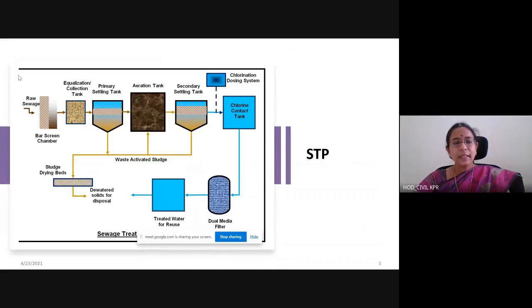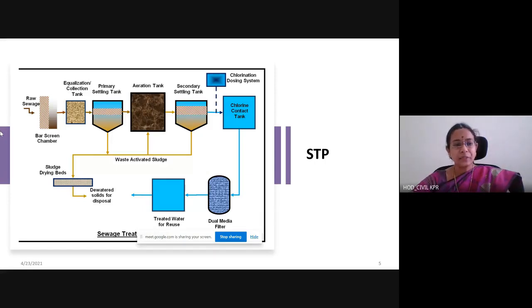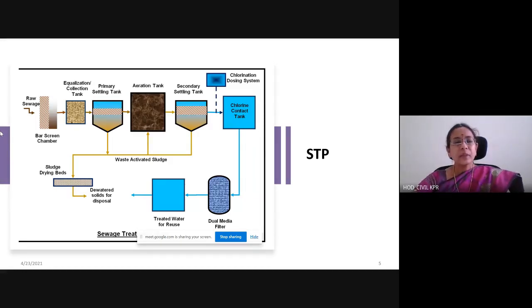When raw sewage enters into the treatment plant, we first usually have a bar screen or some other screen chamber. This screen chamber is especially used to remove the debris or bigger size particles, such as stones, paper, or some other plastic materials. Screen chamber is the first step of treatment. When the sewage treatment plant receives sewage from more than one part of the industry or household, it is collected into a separate tank called a collection tank. Here, sewage from various parts are put together and equalized.